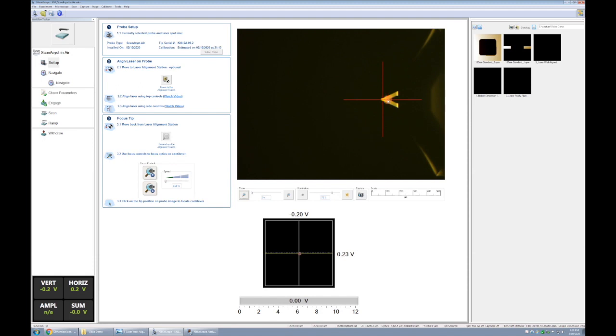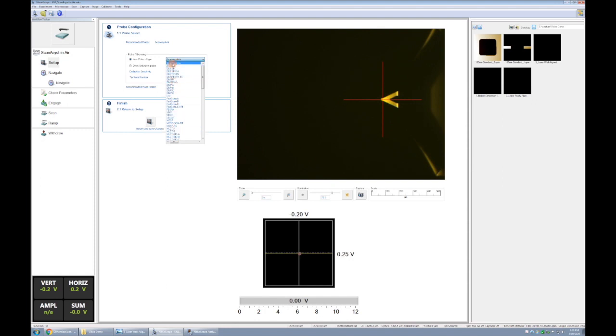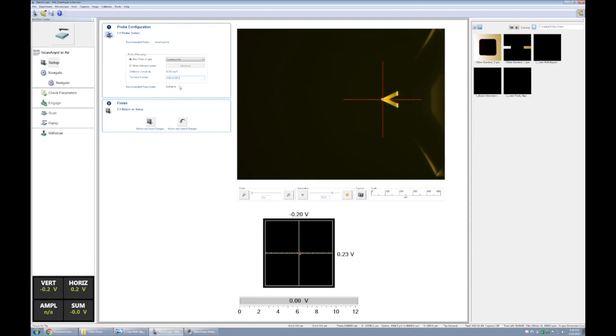If your cantilever is forward, maybe over here or here, that means that your probe slid forward in the probe holder, and you'll want to take it out and reset it. Okay, with that said, we'll now select the probe, and we're using a scan assist air probe. It's listed first, and then everything else is listed alphabetically. This is the one that we'll use for peak force tapping mode. And then we'll enter a serial number for ourselves. So KNISA for scan assist. It's my ninth pack, and the second probe in that pack. And we're using the recommended probe holder, the DAFM-CH. That's just the standard probe holder. We'll return and save changes.